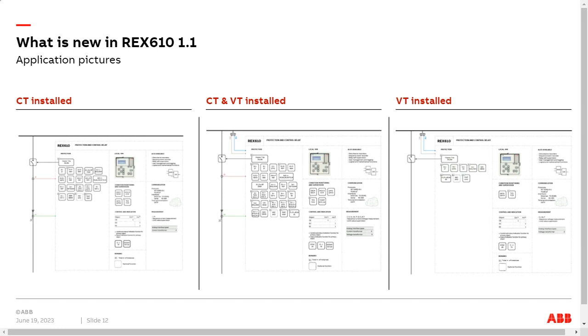So basically the philosophy is the same: depending on the hardware, it will open up the available functions. So even if you modify a device, for example, you have a device with the CT module installed and you add the VT module on-site, the device will directly allow you to use the functions there. You don't need to contact the factory or get any updates or anything like that. You only need the module, you put it in, and then you can use PCM600 to configure the new functions that are available there.